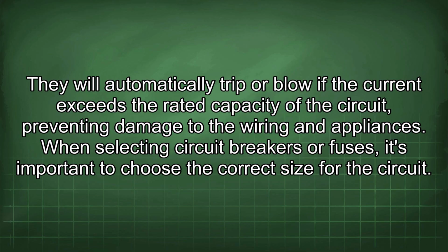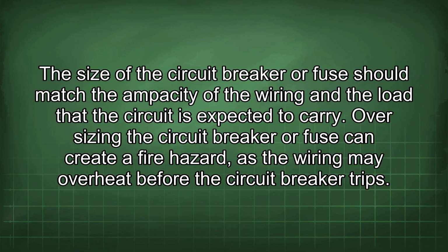wiring and appliances. When selecting circuit breakers or fuses, it's important to choose the correct size for the circuit. The size of the circuit breaker or fuse should match the ampacity of the wiring and the load that the circuit is expected to carry.